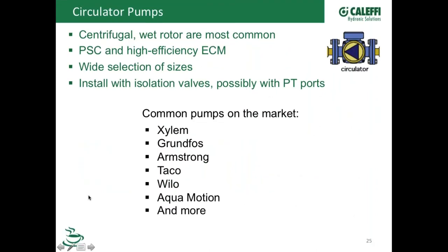Now, just generally about some typical pumps, we talked a little bit about the choices out there. Pretty much every major pump manufacturer, even smaller pump manufacturers, now have an offering of both the standard three-speed or four-speed pumps, as well as the Delta P pumps, and a couple of Delta T pumps that are out there on the market. So really, you should be able to find a pump for most any application you can come across, and certainly, call your reps or your wholesalers to help with the selection.